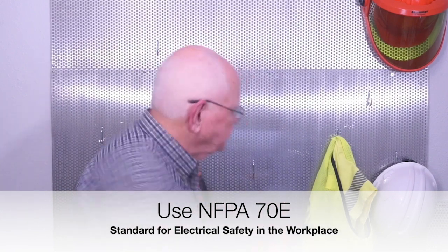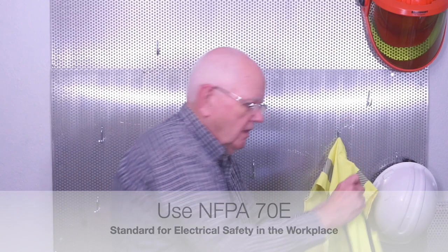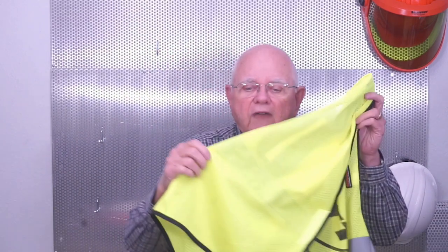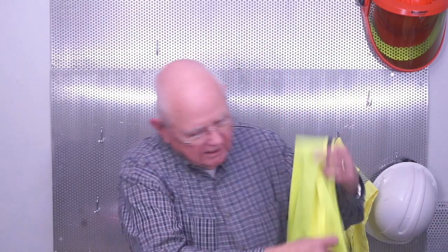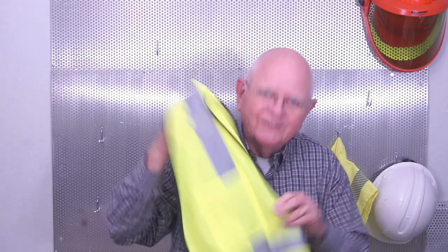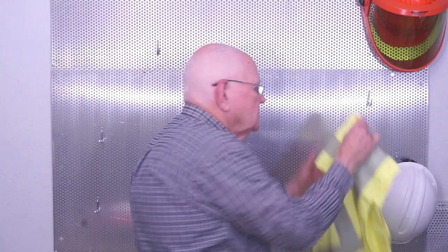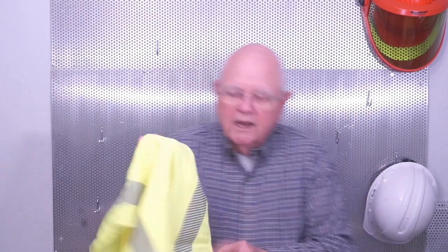Very common out on the job site, right, is we have to wear our high-vis vest. And somewhere here's all the visibility. There we go. And so we have to wear our high-vis vest. Now, this is not arc-rated. So I could not wear this if I were exposed to an arc flash hazard. However, I can buy an arc-rated vest. So here's an arc-rated vest, and I can use this one on an outer layer of my clothing if I'm exposed to that arc flash hazard.